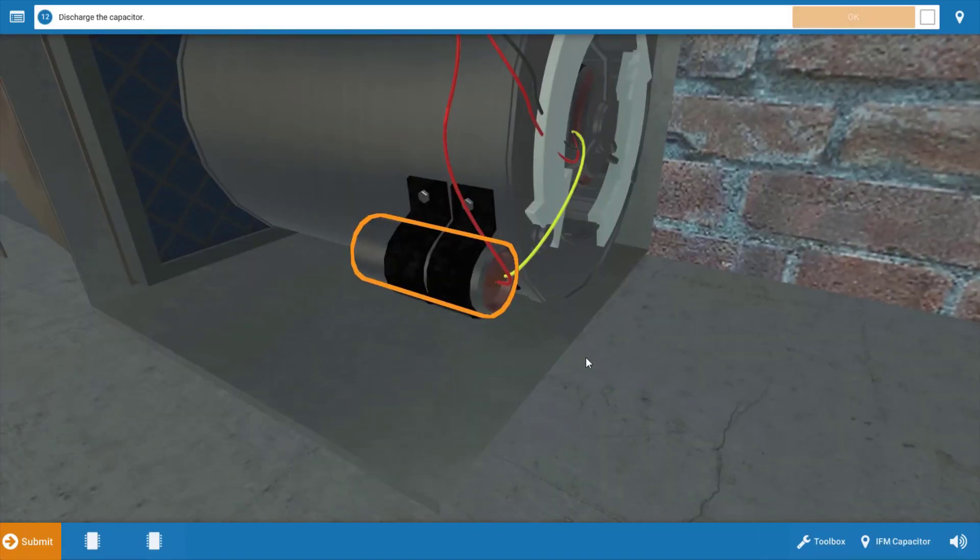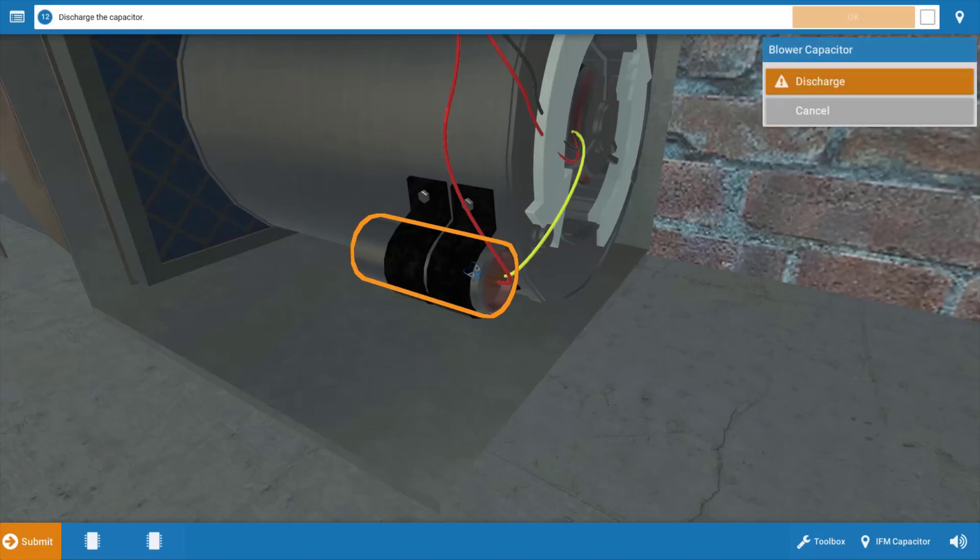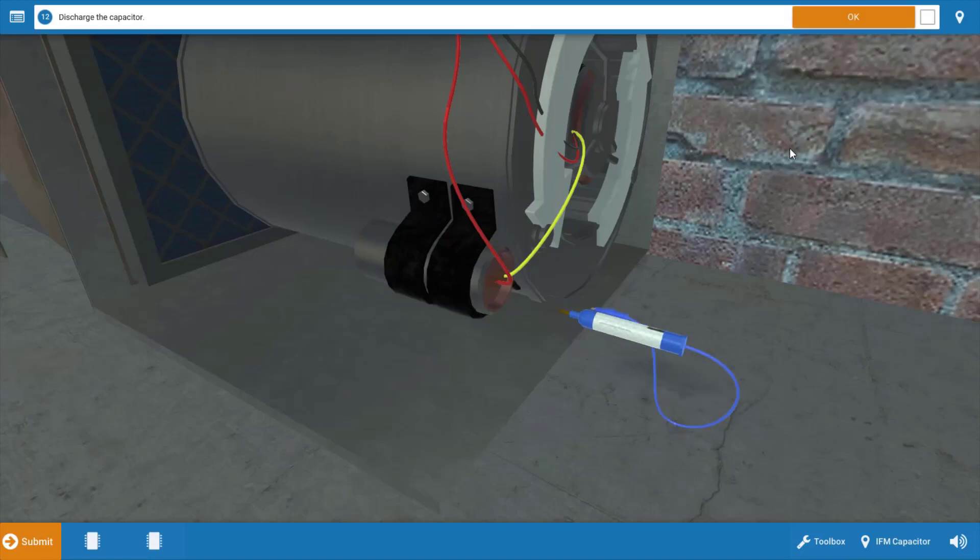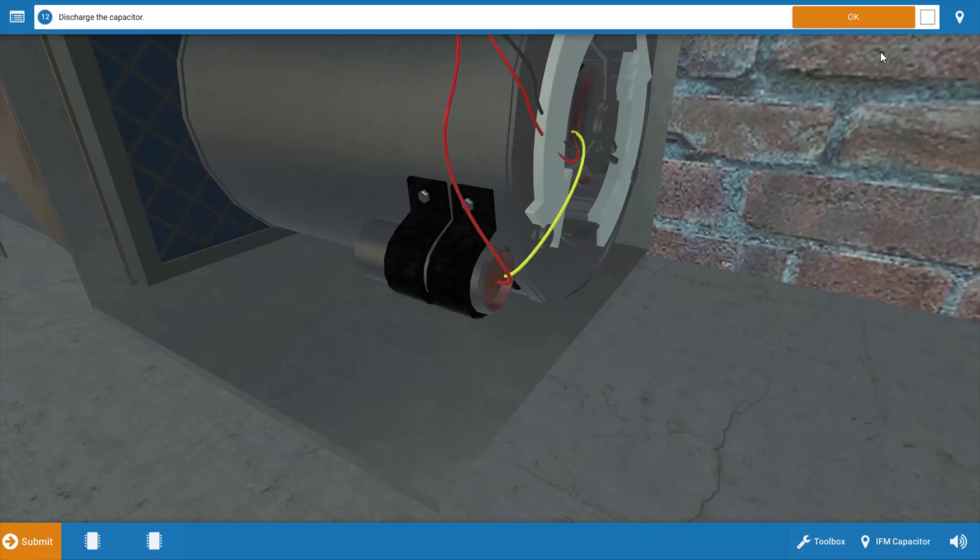Next, we need to discharge the capacitor before handling it. When the power is shut off, the capacitor can still hold a charge, and this could result in electrical shock to the technician. So this is an important safety consideration. Click on the capacitor and click discharge. There's a convenient capacitor discharge tool on the market that's very inexpensive, as opposed to using a screwdriver, which could potentially damage the capacitor or the screwdriver.